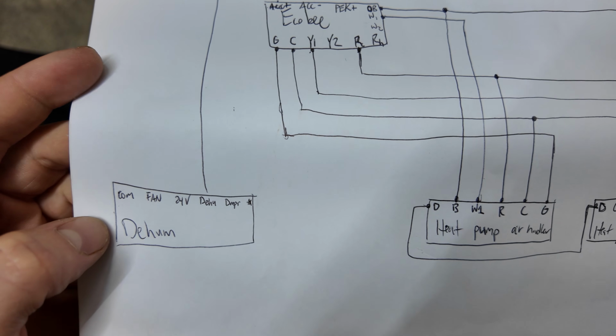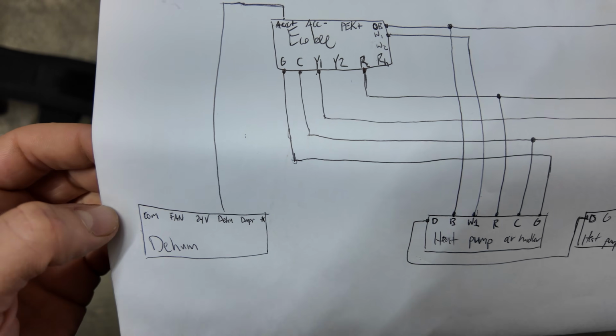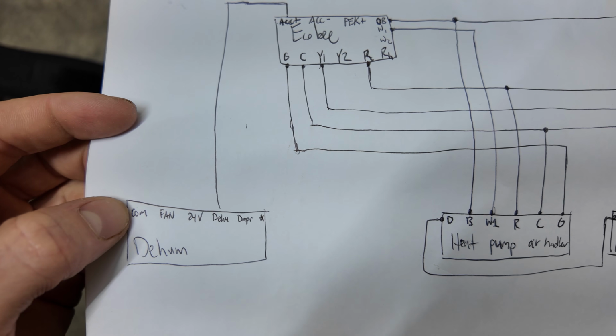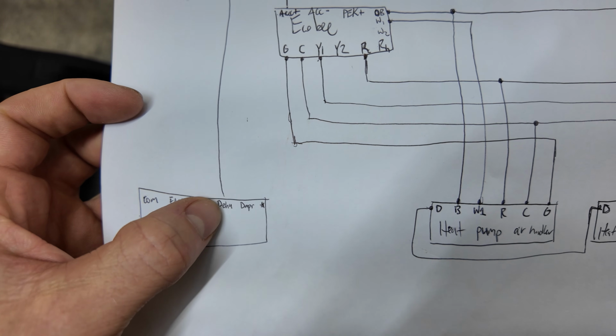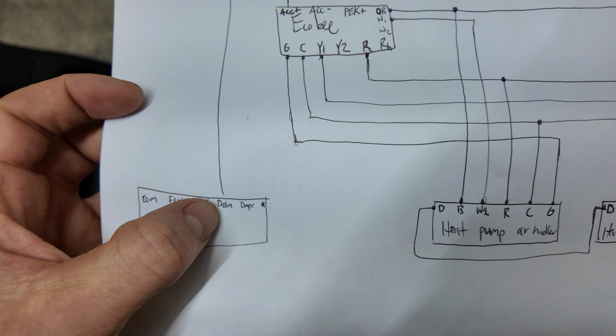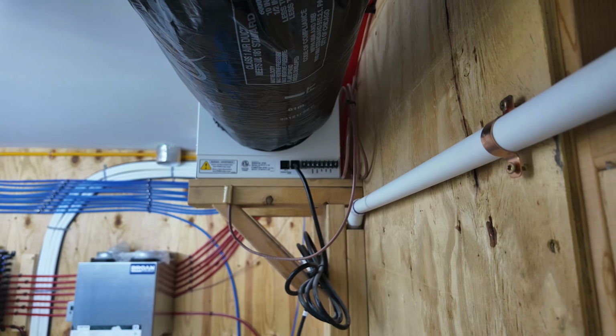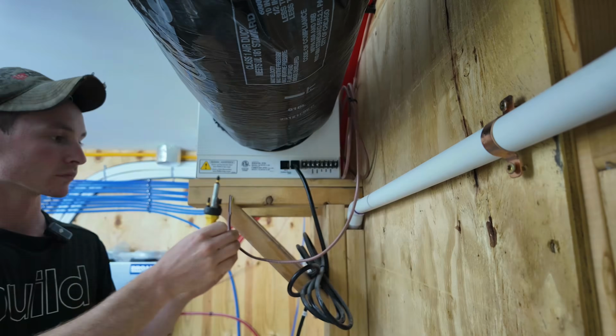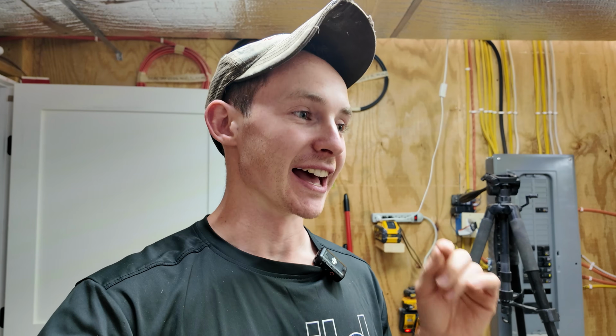Honestly, the dehum instructions do not give much information at all, but it has its own 24 volt transformer included, and I think it should work if just a 24 volt signal comes to this dehum port. So I'll just strip one conductor from that 18/8 wire for now. It's got 8 conductors, so I have plenty of wires in case something ever happens and I need an extra, and wire that up to the dehum port terminal. Once I get my main air handler hooked up for the heat pump, I'll be ready to test this thing out.